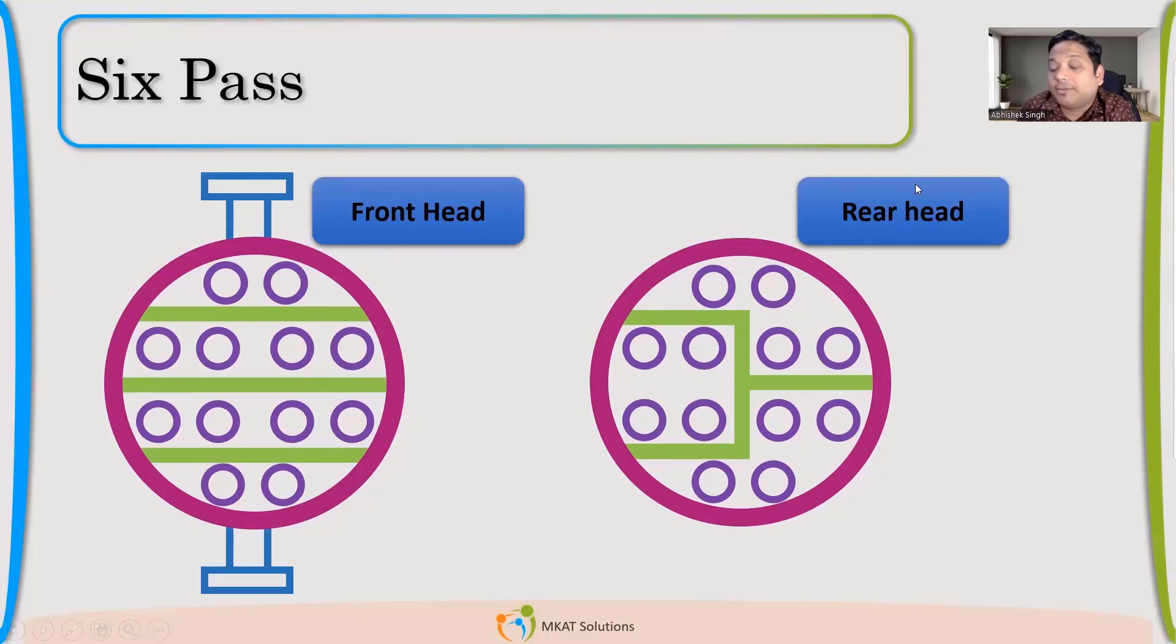In the rear side, there will be one less than what is there in the front. Now you have to just arrange the partition plate such that the number of tubes in each pass is equal. And then your job will be done.